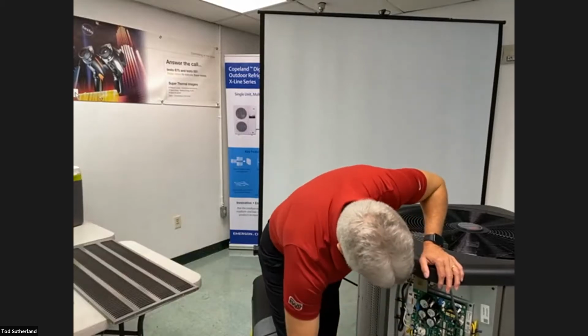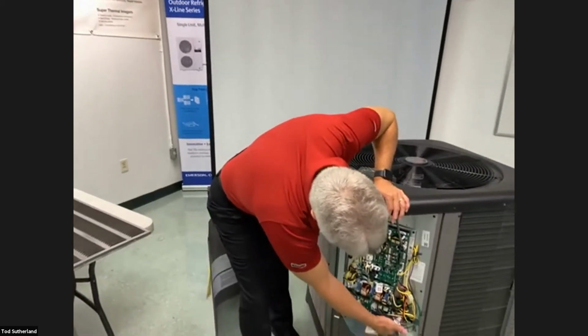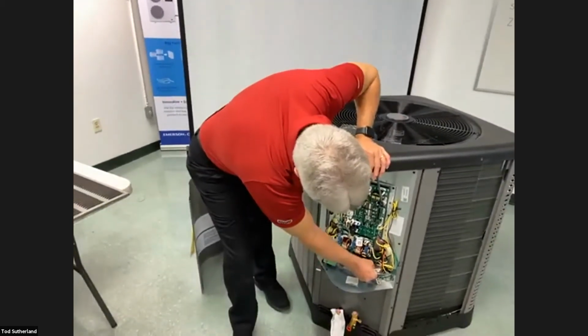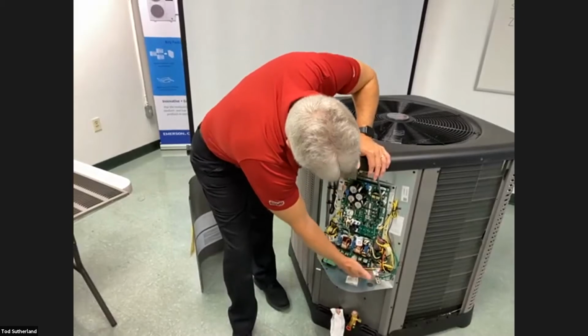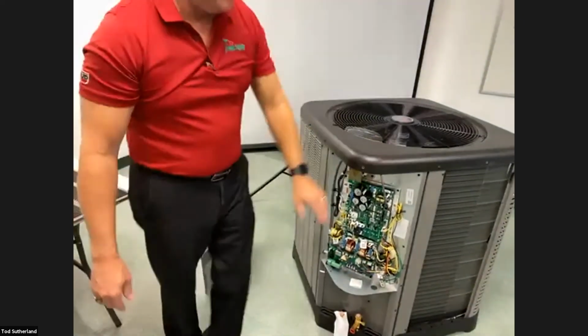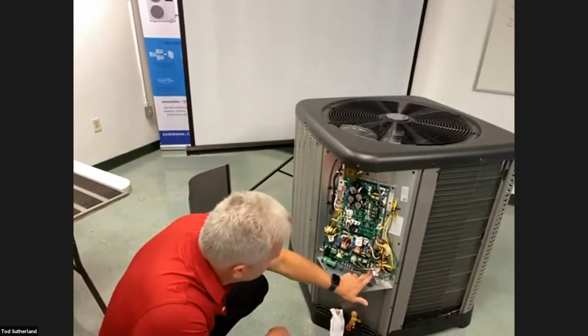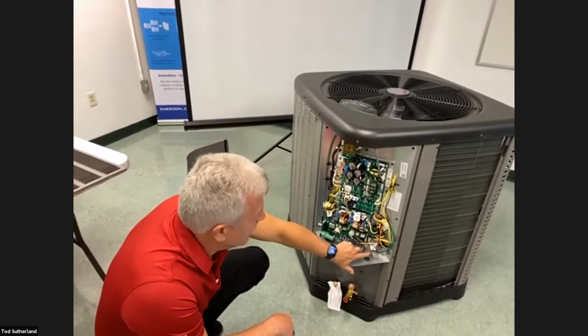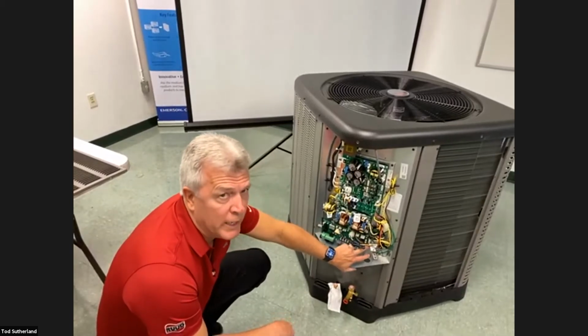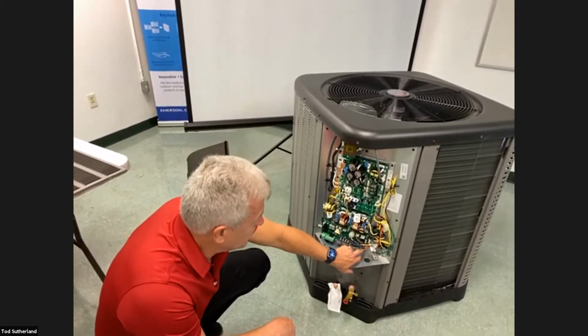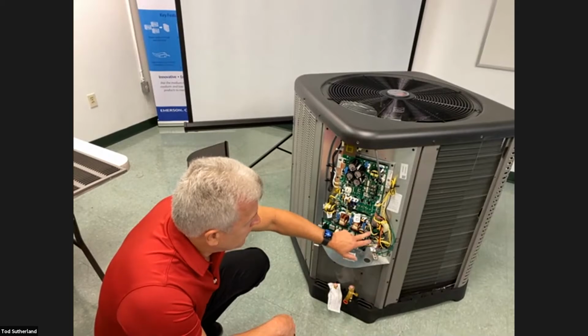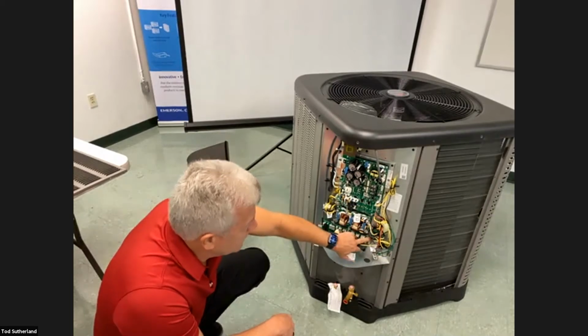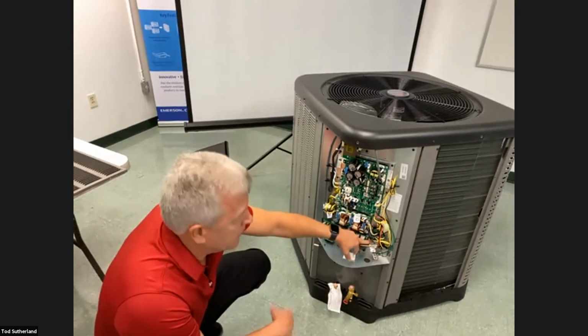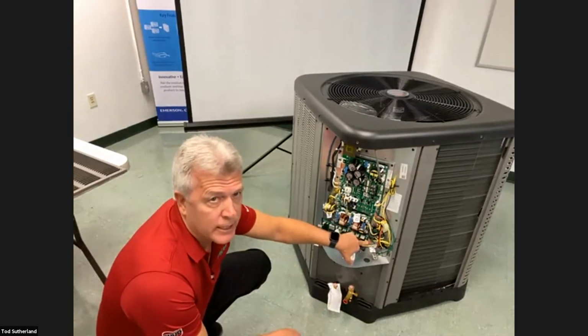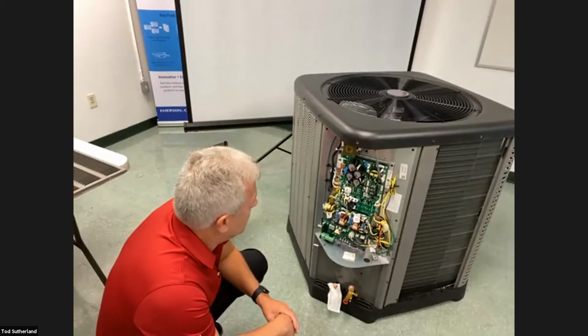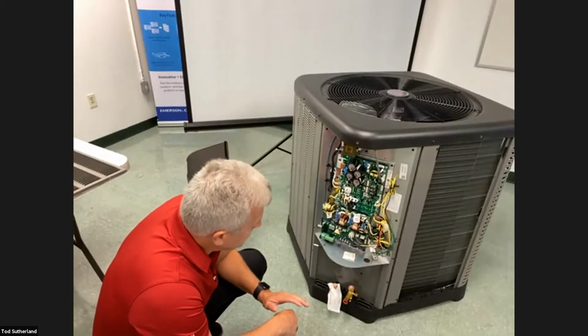Okay, your high voltage simply comes into here and goes right into here. Okay, be careful when you're screwing into there. That's a plastic junction joint there. So when you bring your high voltage wires in here, I've had a couple guys that are bearing down on these way too much, and you can risk stripping these, or sometimes they get loose and these wires at the top come out. And we'll get into a little bit more about the diagnostics there. Well, we'll actually kind of jump right into that now.